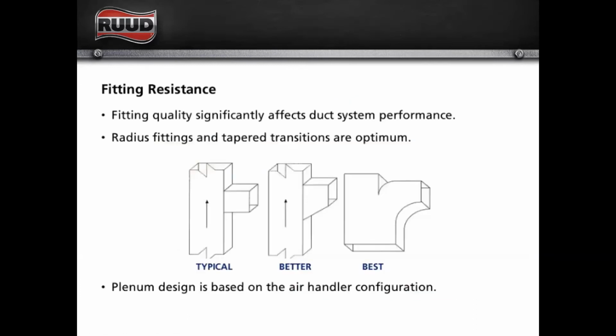Just like the runs, the hard pipe is the same way too, right? If somebody's using 3 or 4 elbows to get somewhere, that can cause problems too. But it takes a lot more effort to do that than it does with a flex run. Fitting resistance also affects duct system performance.